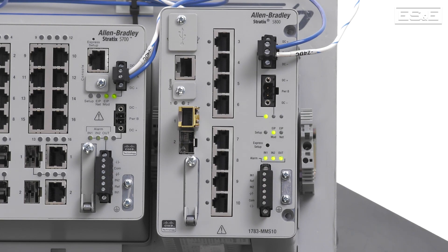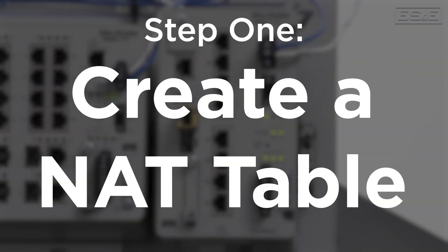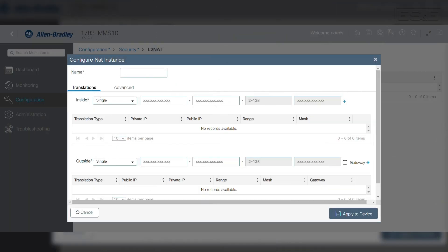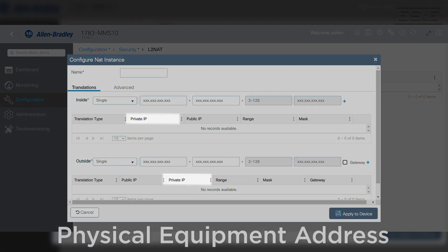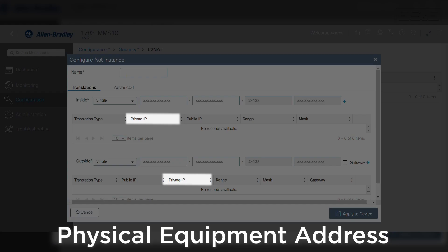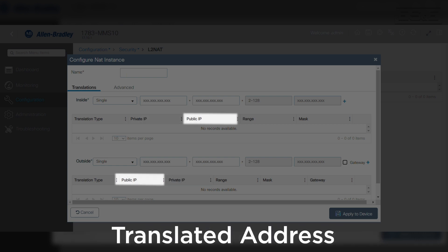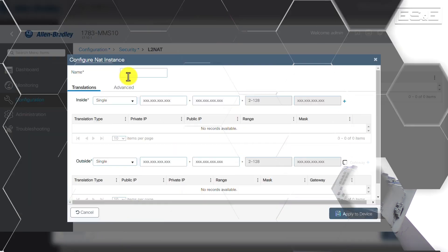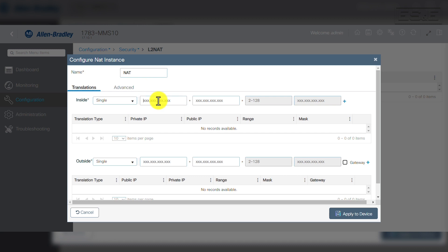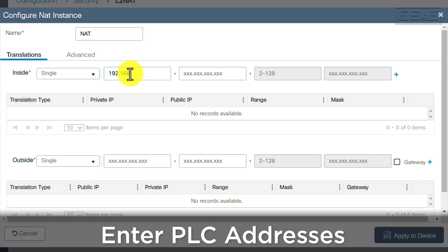The switch is set up in three steps. The first step is to create a NAT table. Within the NAT table, we need to provide the actual physical address of the equipment on the private side, then provide what the translated address will be on the public network. This will allow the public network to see the IP address of the translated IP on the public network. In our example, we will be translating a PLC from 192.168.1.110 to 10.6.10.10.